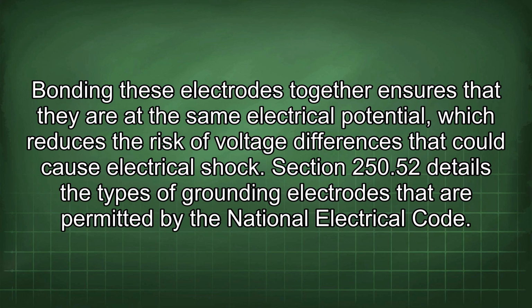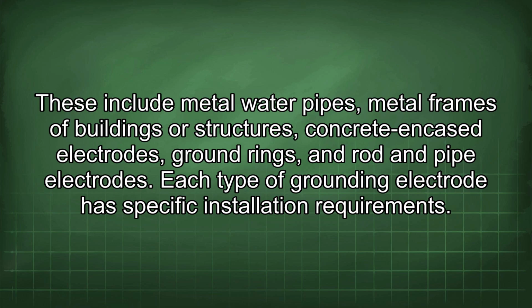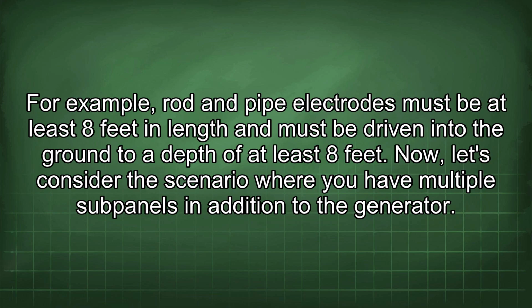Section 250.52 details the types of grounding electrodes that are permitted by the National Electrical Code. These include metal water pipes, metal frames of buildings or structures, concrete encased electrodes, ground rings, and rod and pipe electrodes. Each type of grounding electrode has specific installation requirements. For example, rod and pipe electrodes must be at least 8 feet in length and must be driven into the ground to a depth of at least 8 feet.